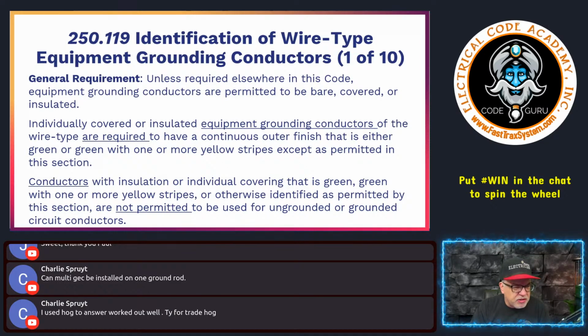Charlie, can multiple GECs be installed to one ground rod? Sure. You have to have separate clamps if you want, but electrode is electrode, right? So it doesn't matter how you're feeding into it. Okay, so I could have two panels and one grounding electrode system, let's say ground rods. The first one doesn't meet 25 ohms or less, so I install a second one if that's my option, and I install it 6 feet away. I drive it 8 feet into the ground, right? And if I want to go to those ground rods with multiple panels, who cares? Lightning doesn't care. It's just trying to get to that earth, right? For lightning transient surges, it doesn't matter. So anyway, hopefully that answers that question.